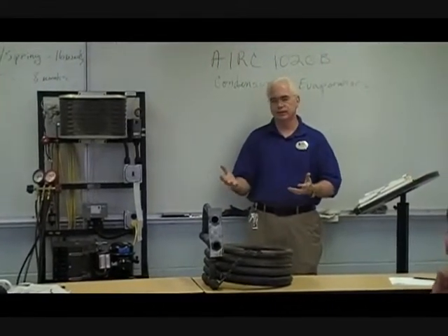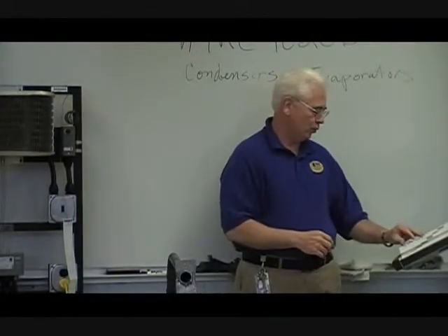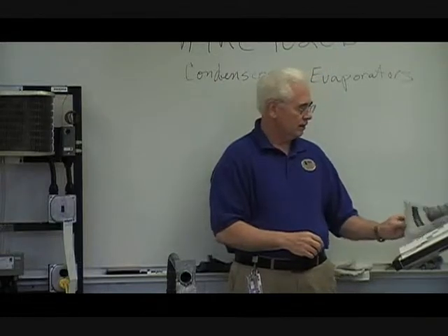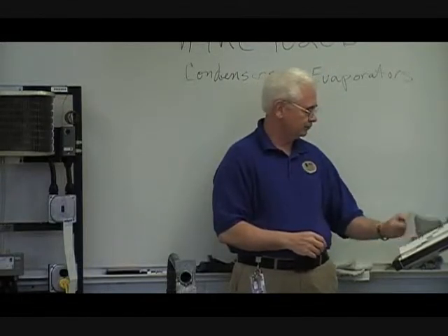A common service procedure in residential HVAC and light commercial and even commercial HVAC is to clean that condenser coil. Now, that's really important. That's a common service procedure. It actually needs to be done at least once a year, depending on the conditions. If it's really dusty or dirty conditions, it may need to be cleaned more than once a year. But cleaning that outside condenser coil to keep that coil clean is really important. Any questions?